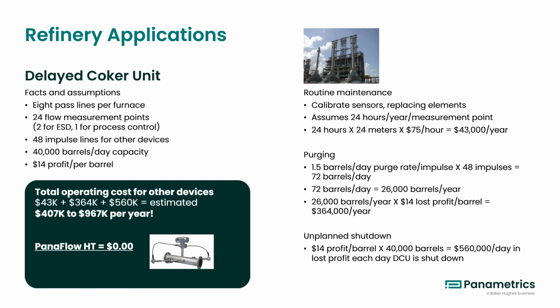With the Panaflow HT, it is zero. To understand the operating cost, it could be either the routine maintenance, purging, or an unplanned shutdown. For maintenance, this work would include calibration of the sensor and sometimes having to replace the sensing element. Assuming 24 hours per year per maintenance point, based on 24 hours times 24 meters times a labor rate of $75 per hour leads to $43,000 per year.